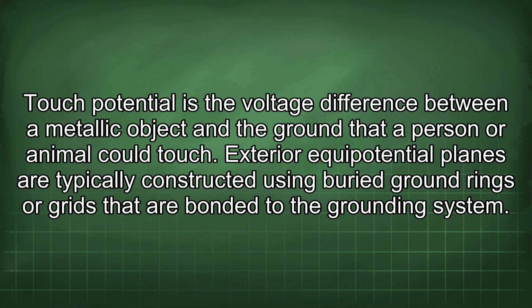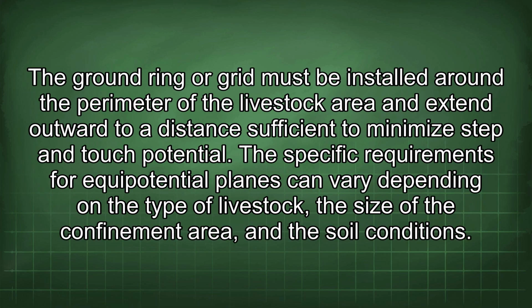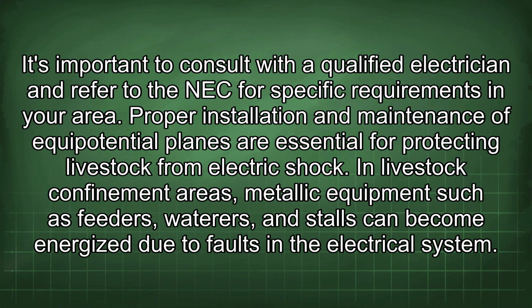Exterior equipotential planes are typically constructed using buried ground rings or grids that are bonded to the grounding system. The ground ring or grid must be installed around the perimeter of the livestock area and extend outward to a distance sufficient to minimize step and touch potential. The specific requirements for equipotential planes can vary depending on the type of livestock, the size of the confinement area, and the soil conditions. It's important to consult with a qualified electrician and refer to the NEC for specific requirements in your area. Proper installation and maintenance of equipotential planes are essential for protecting livestock from electric shock.